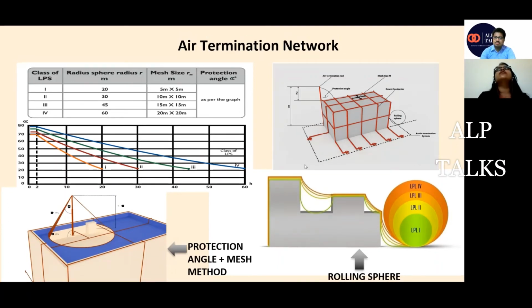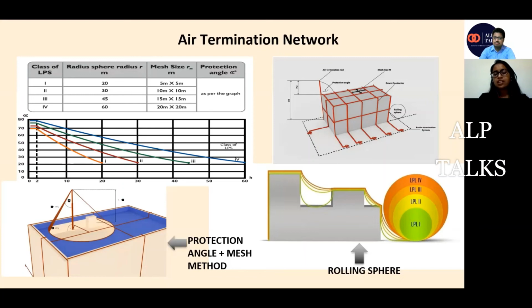What happens in the rolling sphere method? It is a typical method basically. An imaginary sphere rolls over the building. The imaginary sphere's radius is given as per the level: for level 1 it is 20 meters, for level 2 it is 30 meters, for level 3 it is 45 meters, and for level 4 it is 60 meters. So if the building has been designed at level 4, that means an imaginary sphere of 60-meter radius will roll over my building in all the directions.